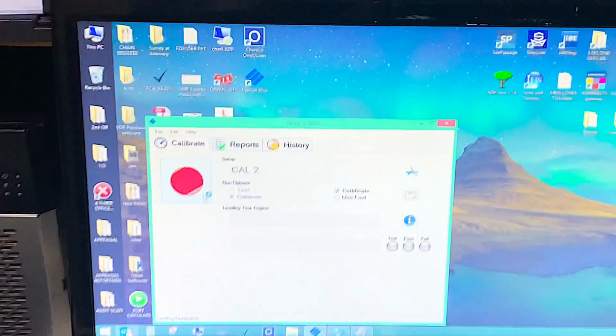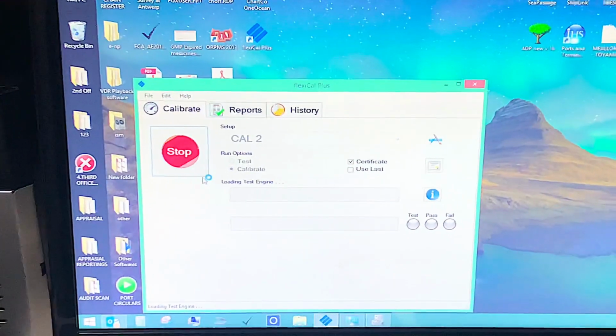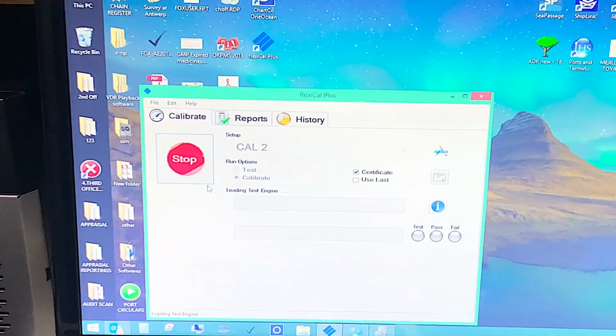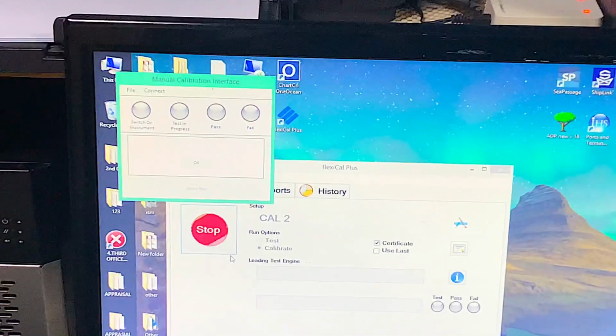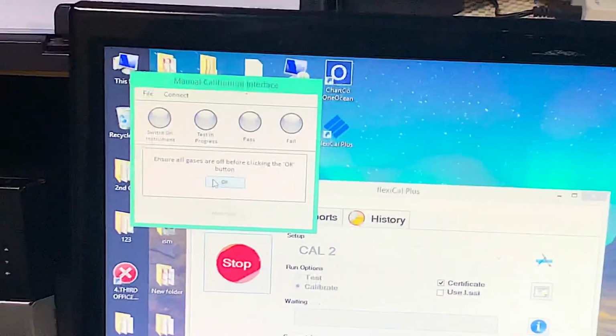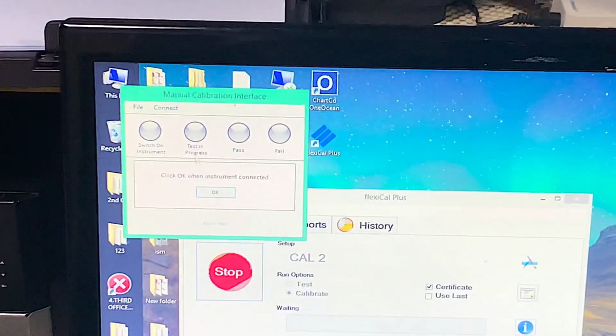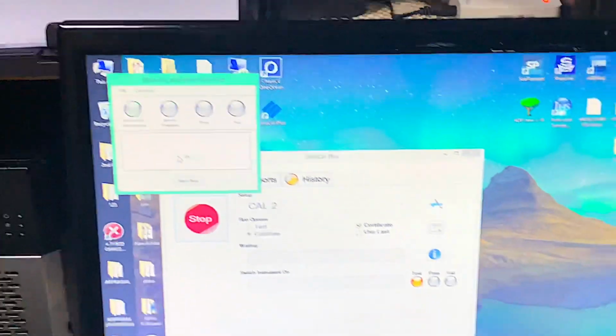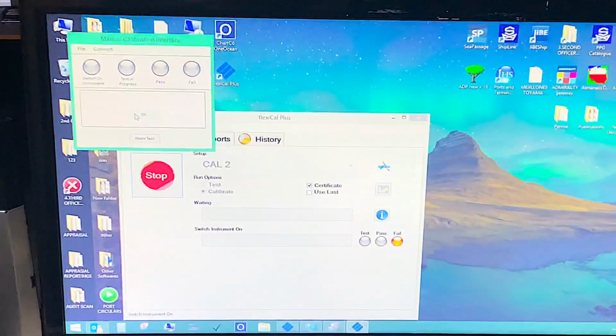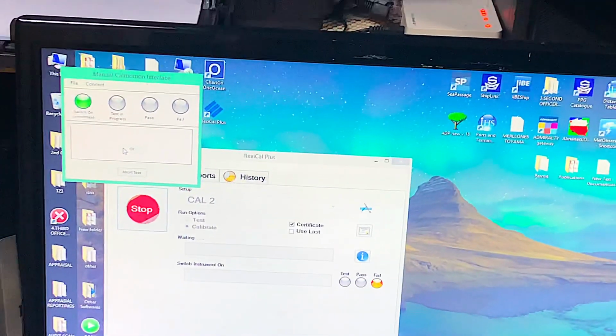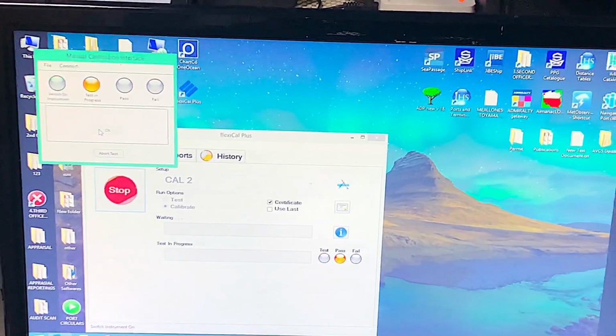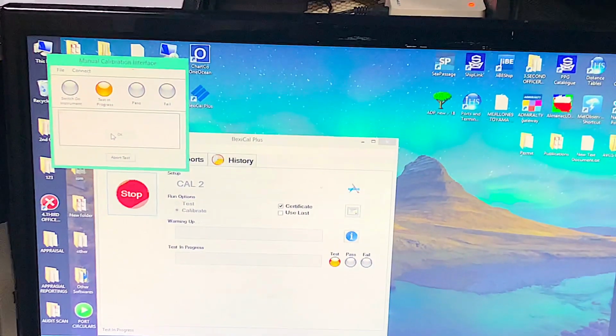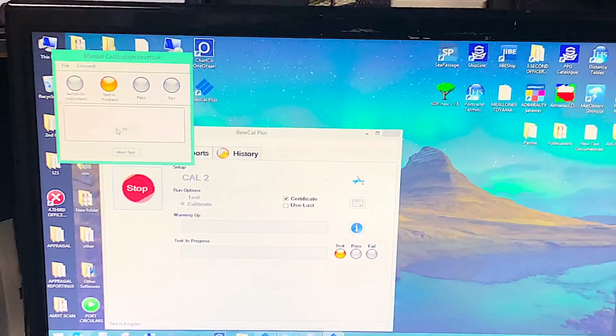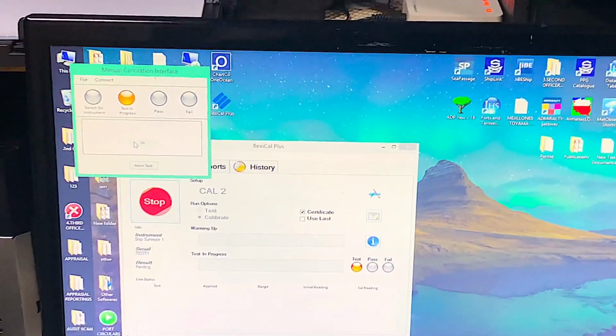Click on start. The system will take a few seconds. Now I have not mentioned over here, but as you can see in the dialog box, click on connect, and then you have to select the port as I have mentioned earlier, that is port 3. Now we have already started with the calibration. You need to calibrate the instrument with fresh air first. So just follow the steps as displayed on the screen.